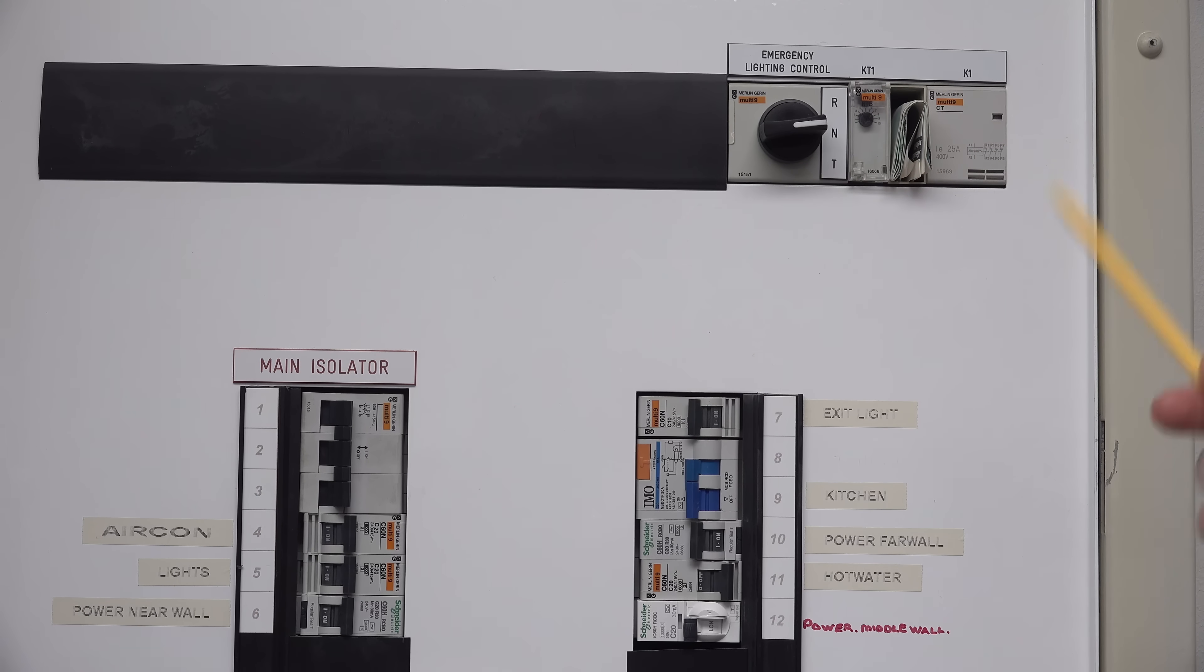And they do come around and test it every 12 months. They physically put it into test mode here. And then it switches over to battery. There's a battery in the light. So even if the power of the whole building fails, all of the exit lights will still operate. That's part of your requirement to keep your lease or whatever, even though I own this place. It's part of the Strata requirements that they have to come around and test this.